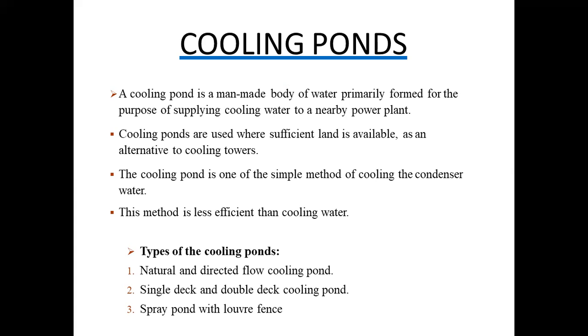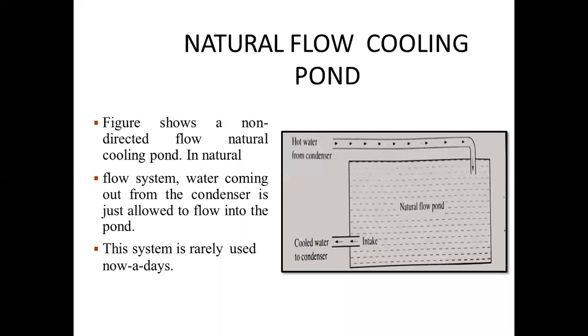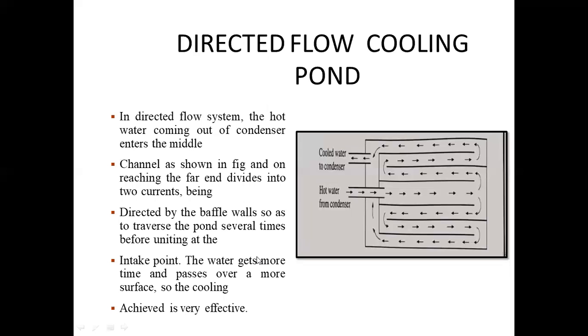So types, there can be three types of cooling pond: natural and directed flow cooling pond, single deck or double deck cooling pond, and spray pond with louvre fence. You can say natural flow cooling pond. In natural flow cooling pond, we are supplying hot water from the condenser, and when this hot water gets cooled, due to density difference, the cold water settles down, and from the bottom side we remove the cooled water. This figure shows a non-directed flow natural cooling pond. In natural flow system, water coming out from the condenser is just allowed to flow inside the pond. This system is rarely used nowadays, but here we are using a directed flow cooling pond.